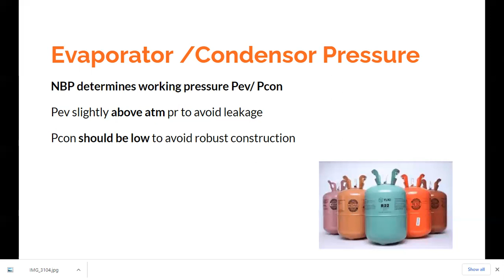Okay, so a desirable feature of condenser pressure is that the refrigerant should give us, within the working temperature range, an evaporator pressure above atmospheric pressure, and a condenser pressure low enough so as to avoid robust construction. This important ratio, PC upon PE, has to be clearly understood. As I said, the working pressures are decided by the temperatures we are aiming for.